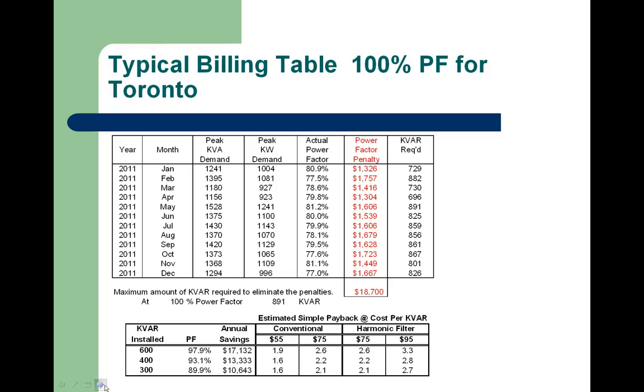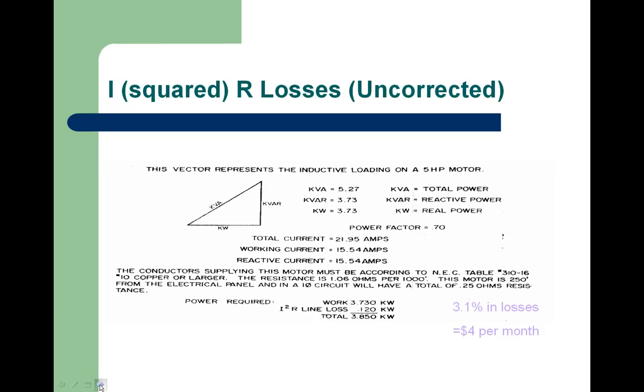One of the things, the next thing we're going to get at, is that what we've looked at right here is primarily demand savings, which is the demand component of the hydro bill. There are some associated savings that one sees by putting in capacitors, and that is I squared R losses. I squared R losses is the amount of energy that's used to transfer amps or current through cables, wires, bus duct from the main metering point to the end load.